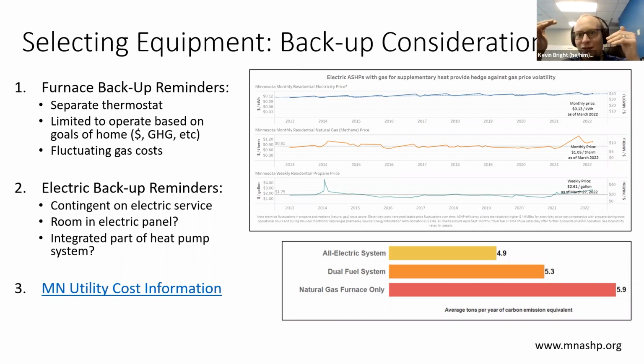That sent a signal to me that this manufacturer is already accounting for the fact that they know how to control the heat pump as well as the electric resistance heat, and I'm not going to be in situations where they're both running at the same time, or they don't know when they should run. That's in comparison to other bids I received, where the contractor said we could cut in a separate electric coil into the air handling unit, controlled through the same networked control, but it wasn't integrated as part of the heat pump system. That concerned me, because ideally the manufacturer of the heat pump and air handling unit are setting up a backup heat system that works. If it's all integrated into one package, that signals to me that they're pretty sure it will all work together and be controlled effectively and efficiently.